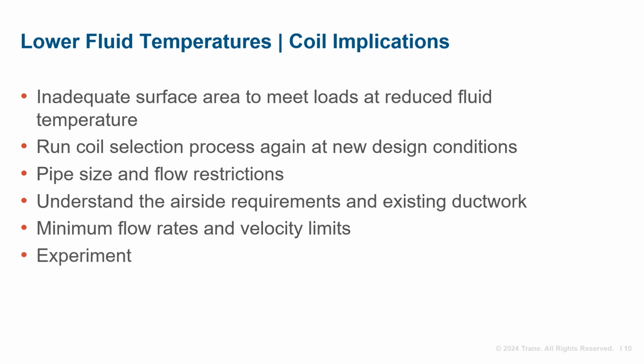Sometimes building owners will take a try and see approach. The systems may have already been oversized. On a cold day, reset the hot fluid temperature and then see where the cold calls come in. Those are coils that potentially need to be replaced or further investigation is warranted.